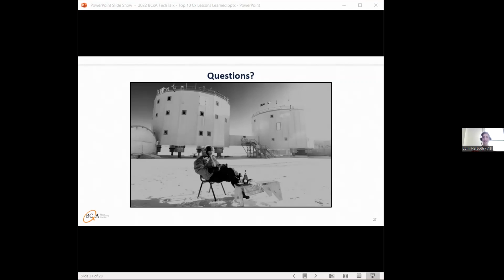So when it comes to that freeze damage on that RTU for the Performing Arts Center, it was turned on and operational, and they were actually having training that Monday when it happened. We all sort of just stepped into training knowing there was a frozen coil, and that was a fun situation to meet the controls contractor who was on vacation. We had gone through and done our initial testing, but corrections weren't done at the time. So that's the point where it was turned on, operating, but the corrections weren't done.